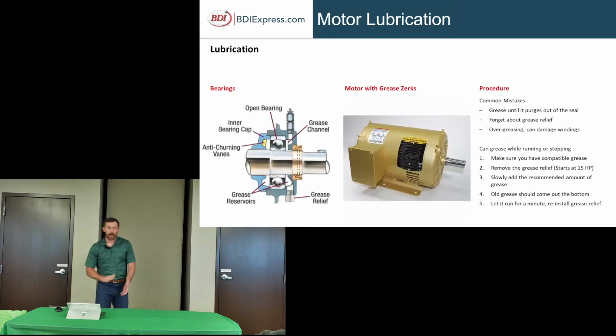There we go. So your motors, 15 horsepower and up, are going to have grease zerks. Some, and I've seen it, kind of depends on the manufacturer, but typically for Baldor motors, you're going to have a grease zerk on there. You're also going to have a grease relief. You always want to make sure that grease relief is unplugged, because otherwise the grease will flow to parts that you do not want to grease, like your windings, and that's going to cause motor failures.